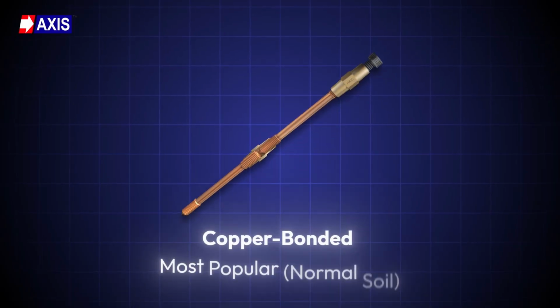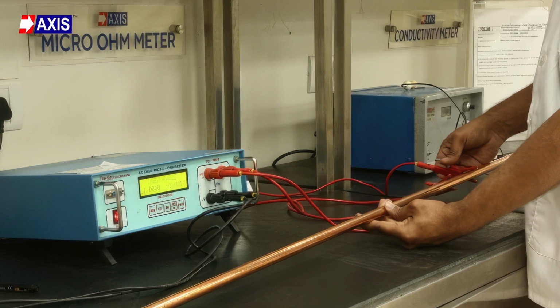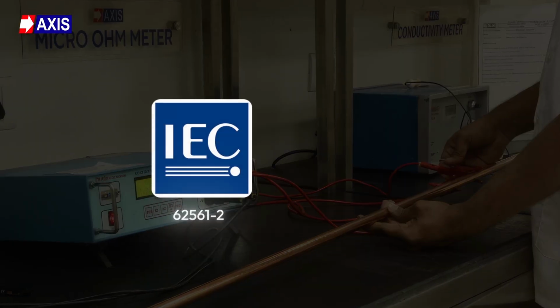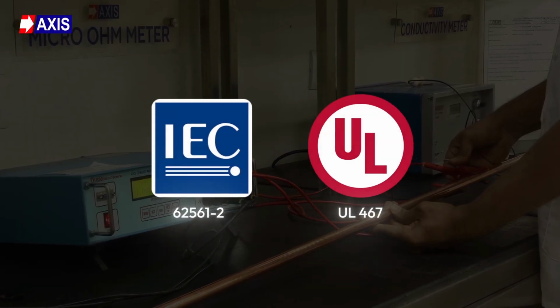In normal soil conditions, copper bonded rods work well. This type is the most popular earth rod used across the world. Axis copper bonded earth rods comply with IEC 62561-2 and UL 467.